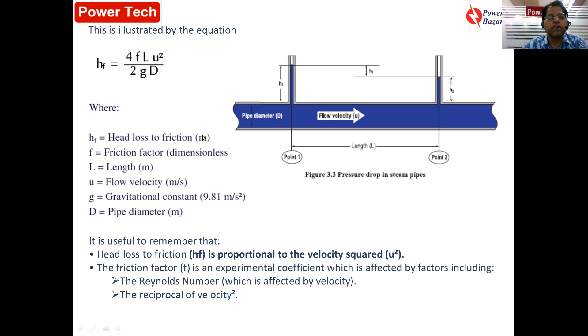Now let us take this example. Determine the pressure difference between 2 points 1 kilometer apart in a horizontal pipework system. In this case, the flow rate is 45 meter cube per hour. So what will be the velocity? As I know, volume flow rate will be velocity into cross sectional area. So if I multiply velocity into cross sectional area, I'll get meter cube per second, which is nothing but volume flow rate. Now diameter is 150 mm.